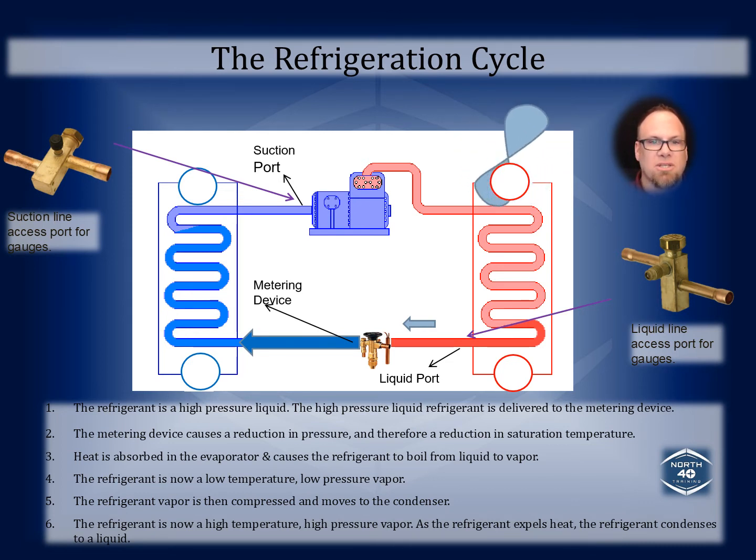And as the temperature is sent up, we're able to measure that. So we're able to check whether or not there's an obstruction based on temperature. We've seen people do that oftentimes when you've got an obstruction, maybe a kink in the line set going through a floor or a small piece of wall where maybe the brick has collapsed on it. All of those scenarios, if you understand the principles behind the thermodynamics and the refrigerant flow, you can diagnose. It makes you a better refrigeration or air conditioning technician to understand this stuff.